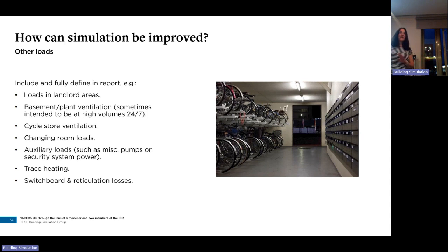Some of these might not be that significant, but for example, a basement plant room can have quite high ventilation rates, and these can often be 24/7 loads, so they can actually be quite significant and make a difference to the rating. Also, trace heating and switchboard and reticulation losses should be mentioned.